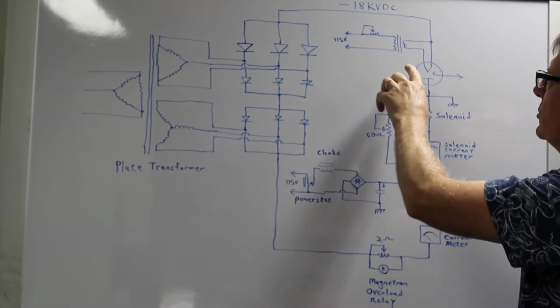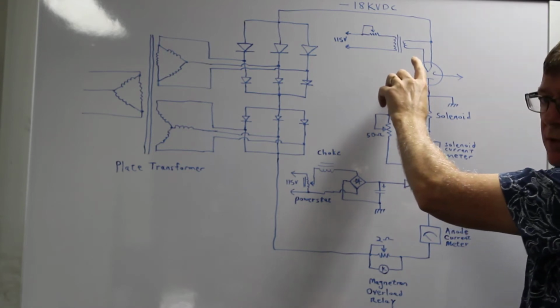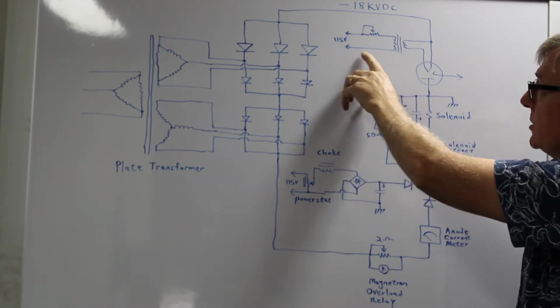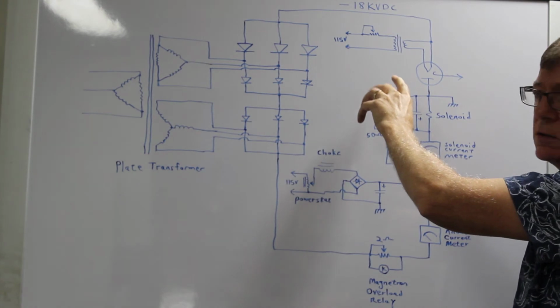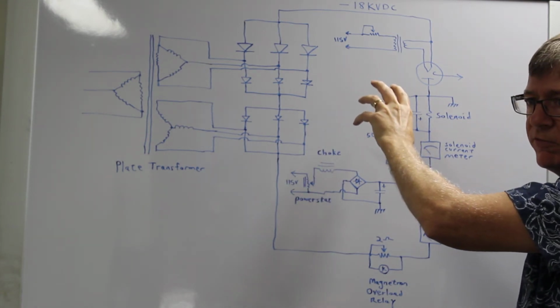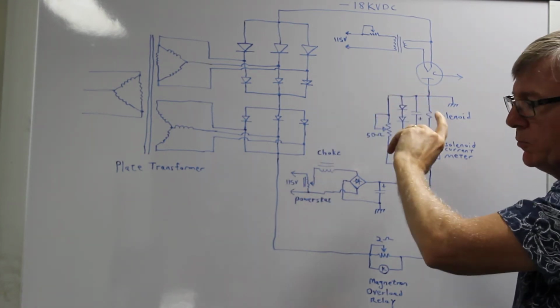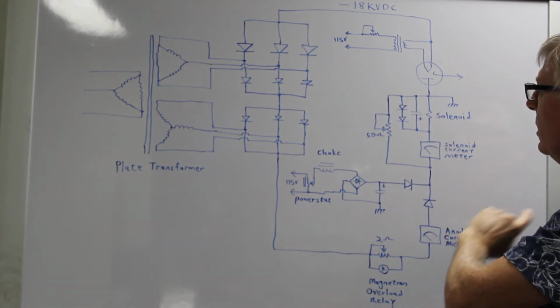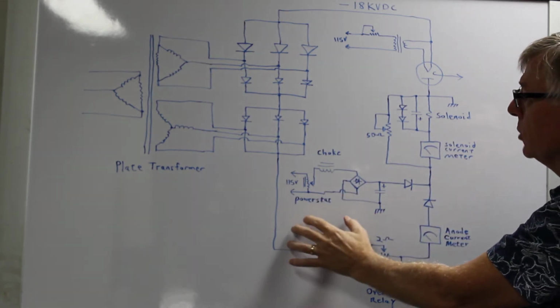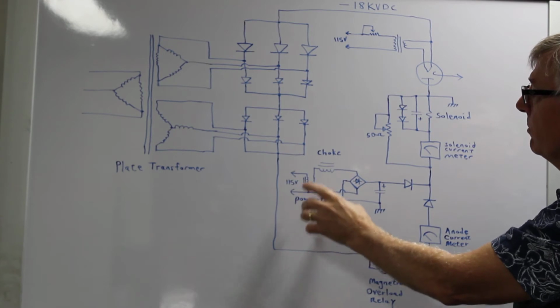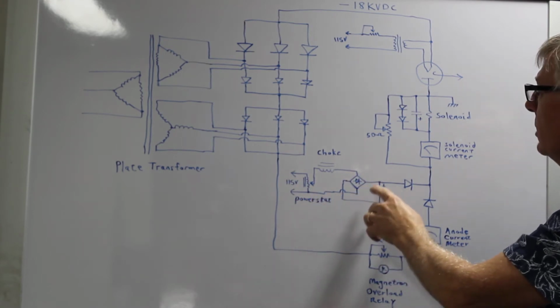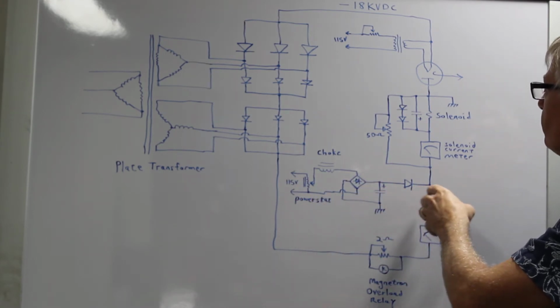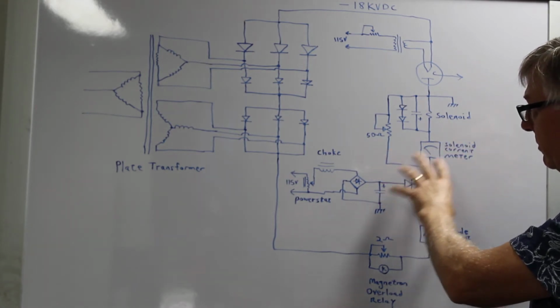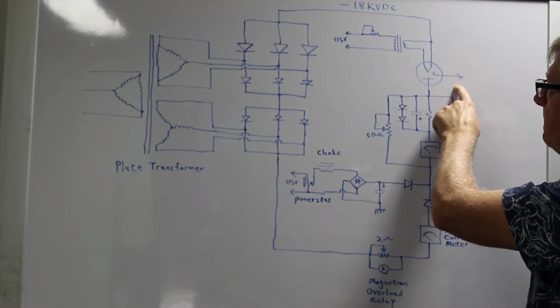You have a filament power supply, which is essentially just a transformer and a rheostat. In some cases, there's an electronic controller for the filament current rather than the electromechanical device. And then we have the solenoid power supply, which is comprised of a powerstat, a choke, a diode bridge, and some filters. And then all of this connects to the magnetron tube, which is here.